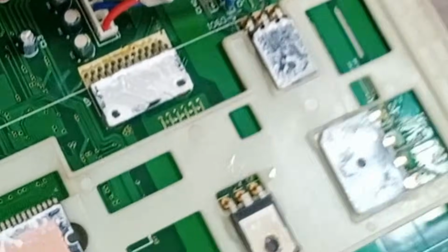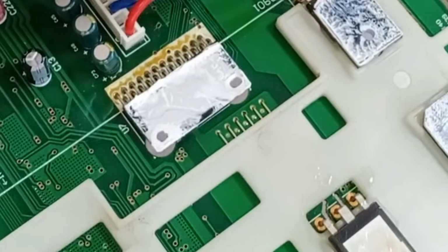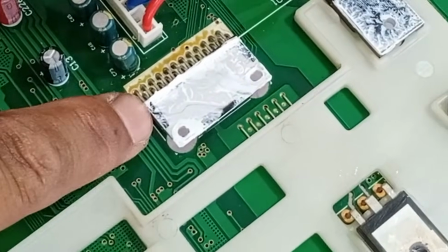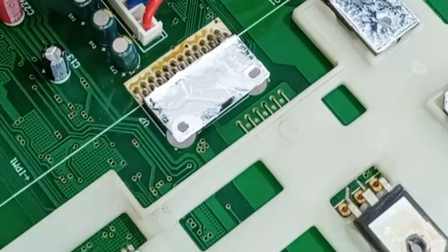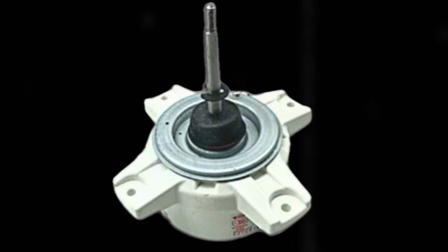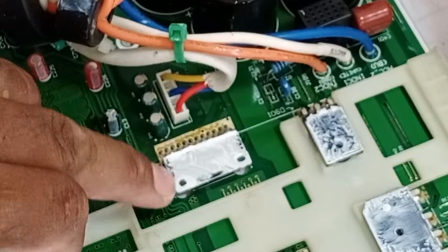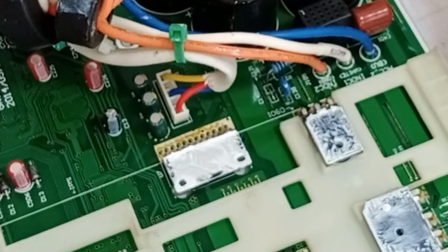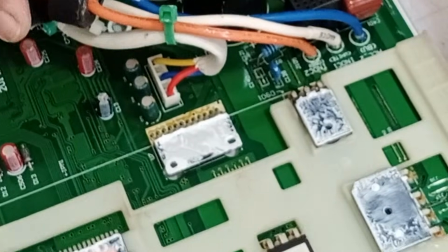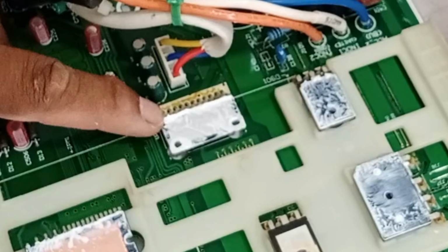You can also see another IC, which is an IPM, Intelligent Power Module, and this IPM is for the DC blower motor. The outdoor unit has a UVW motor installed, and the entire circuit for that motor is located on this outdoor board. If the IPM is short-circuited, it could also cause issues in the circuit.